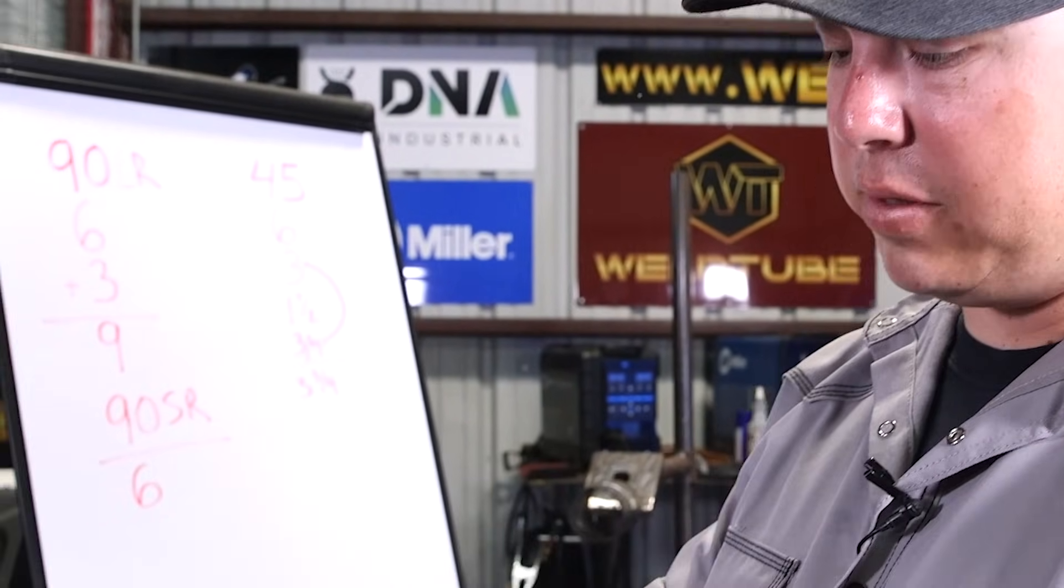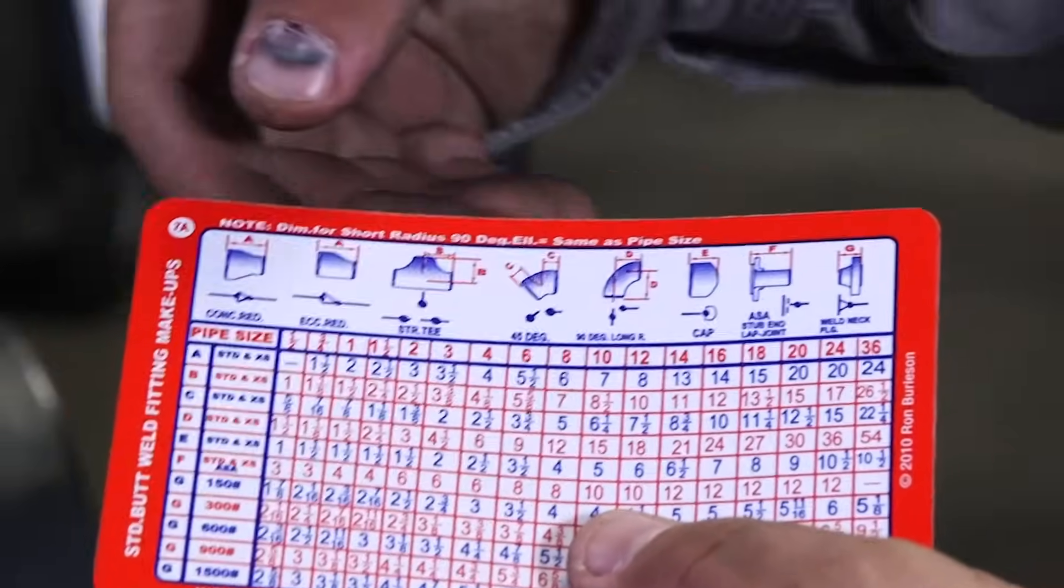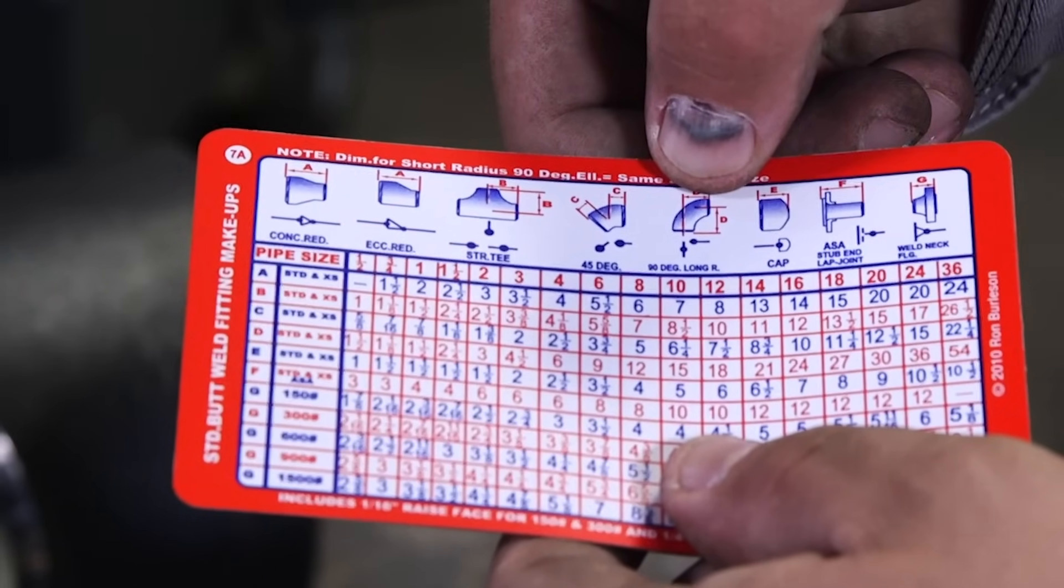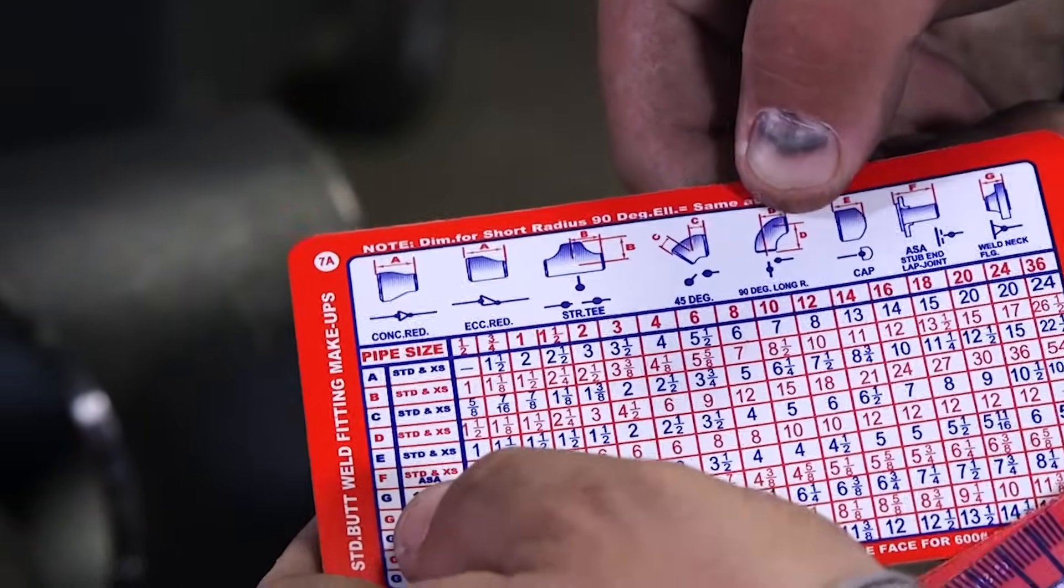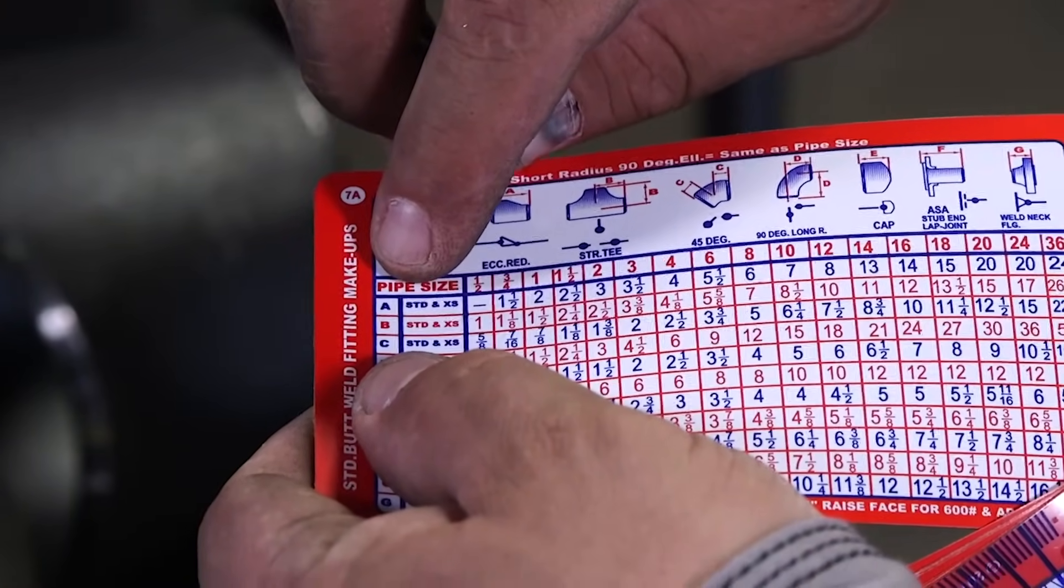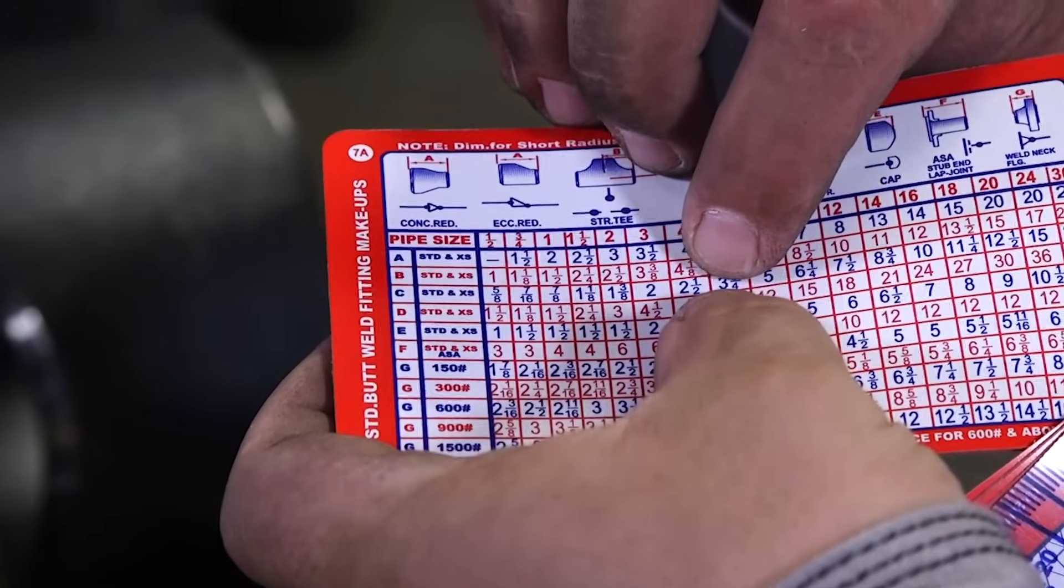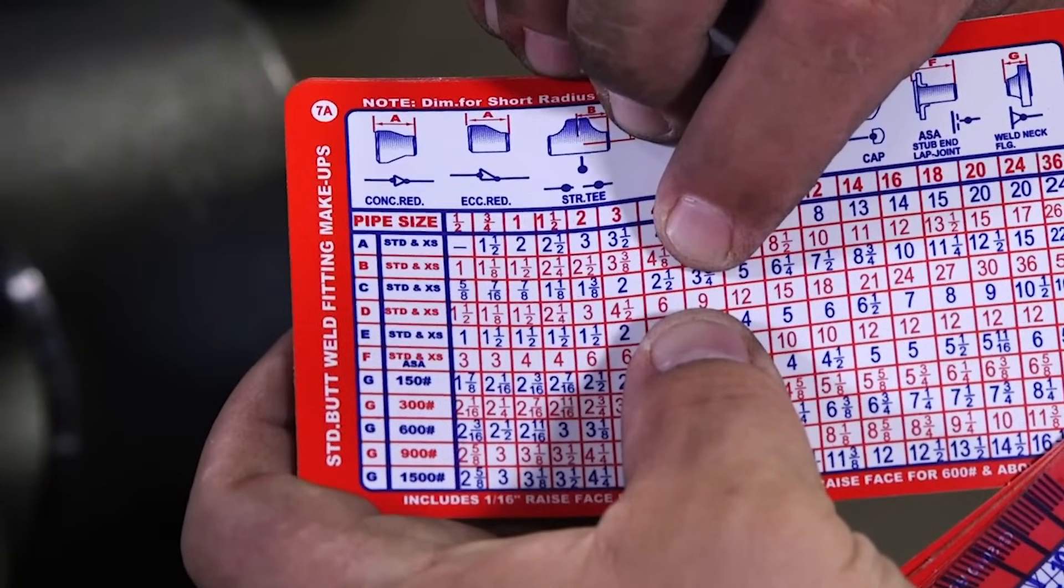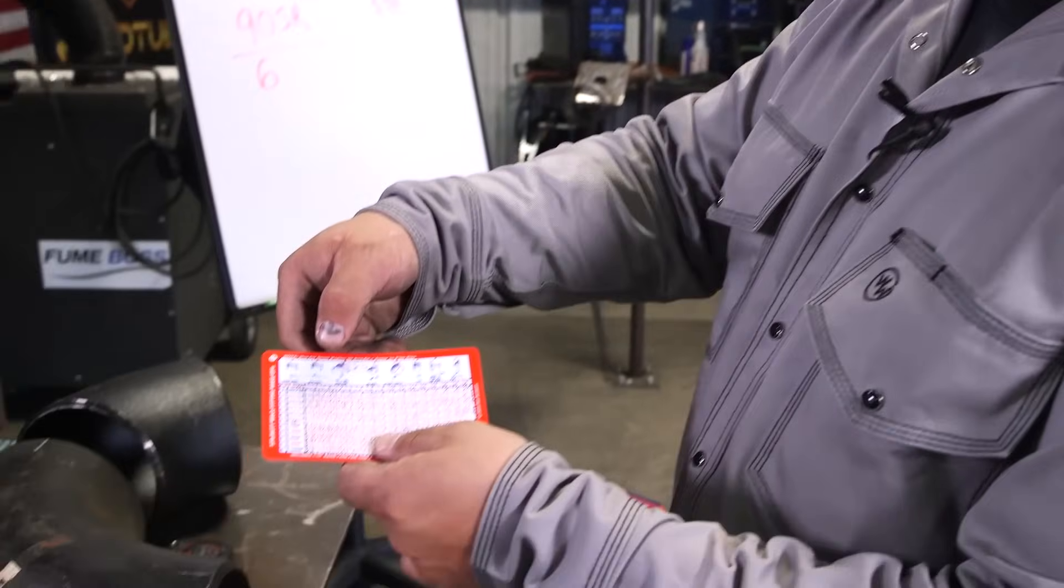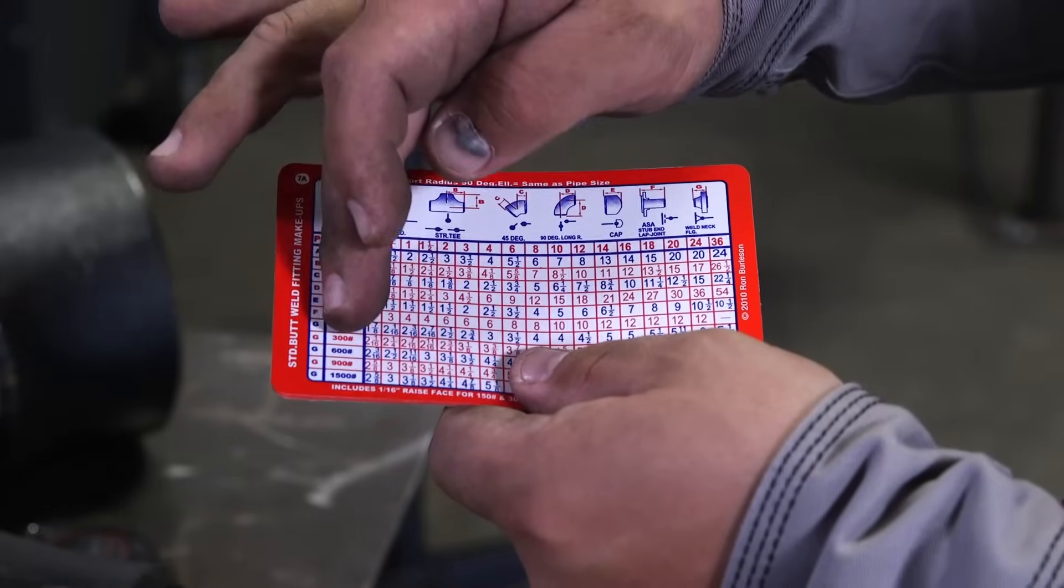Alright, so this is how you find the takeoffs here on the Chico cards. We're going to go to page 7A, which is our standard butt weld fitting makeups here. We're going to go up to top and look for our long radius 90 degree, which has the letter D. We go to letter D. And on this top header, now we're going to find our pipe size, which is 6 inches. Run it down, and there's our 9 inches for our takeoff. And you would do the same thing for 90s, flanges, and any other kind of fitting you're looking to find the takeoff here. It follows the same process. Find the letter, follow it down, and then follow your pipe size on the top header.